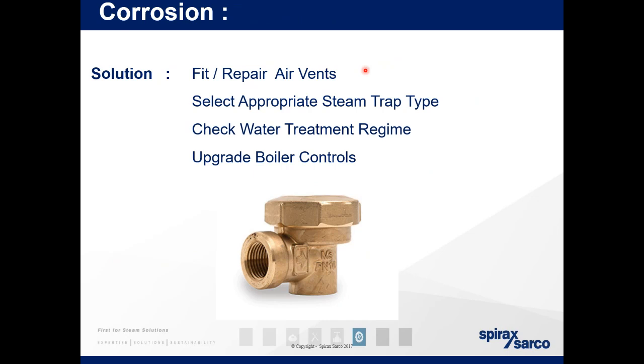So as the boiler drops in level, even fractionally, the control valve and the pumps activate, so it maintains a level with a slower amount. So if you are introducing, say, 100 liters on stop-start, on-off, you'll be introducing, say, 1 liter on modulating. So the thermal shock to that boiler is less. It only needs to heat 1 liter of water, so it makes it more efficient. I'm hoping that explains it enough.